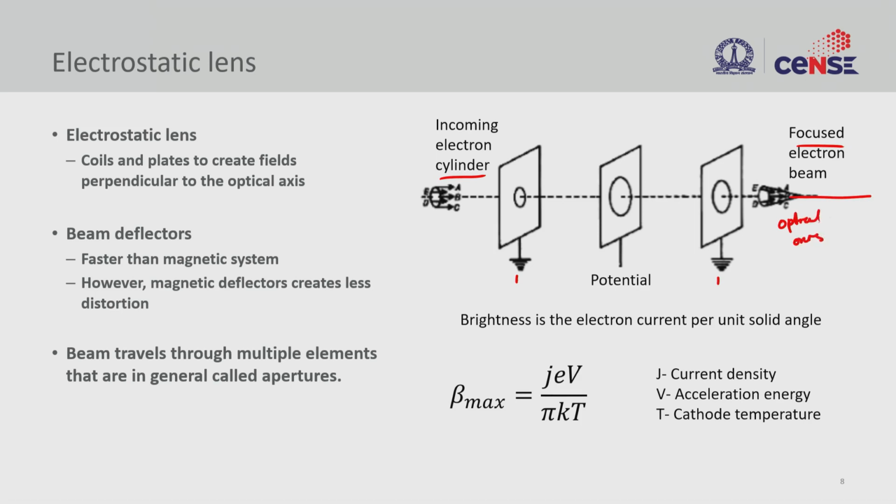If the beam is within the optical axis, you will capture it, and if you put a deflector here and apply a voltage, I can deflect the beam. If I deflect it, then I will not see that beam, or if you do a small deflection, I can change the position of this beam. These deflectors can be realized using electrostatic plates, but you can also use magnetic ones.